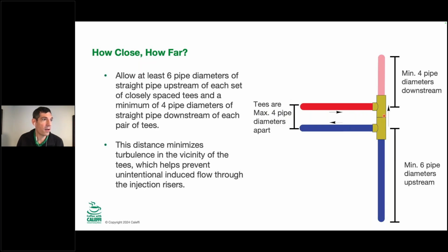Maximum distance right here of 12 inches, maybe, if you've got 3-inch pipe. If you've got 1-inch pipe, that's no longer acceptable. You're going to be beyond that book answer of maximum 4 pipe diameters apart. So another thing that comes up here: 4 pipe diameters apart is the number that we want to use on center from the boiler supply to the boiler return.